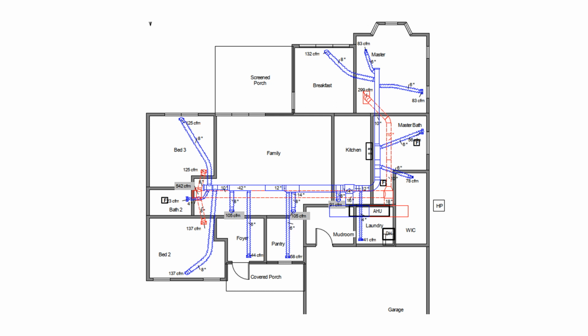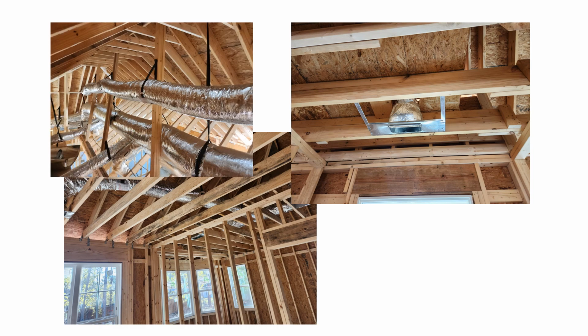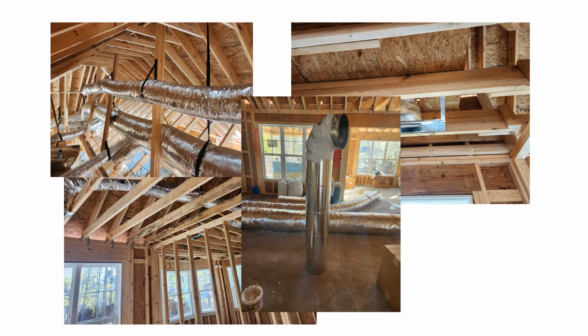Then I drew my duct sketch on Wrightsoft. It automatically sizes the ducts according to my inputs. It accounts for the differences in flex versus hard ducts, and Manual D's maximum velocity limits for supplies versus returns. This is the duct plan deliverable that it displays, and I would use this plan to order materials and start my installation process. Now there's plenty more about that coming up in a future video.